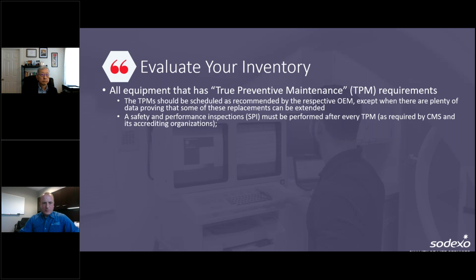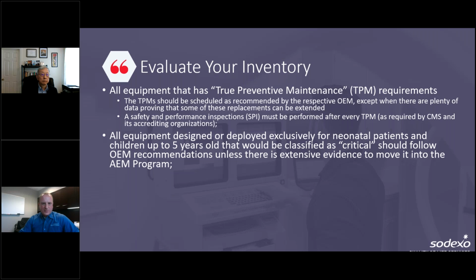So what we want to take into account is devices that what we consider true preventive maintenance. It's not just a safety and functions check. We're looking at items that require repair or replacement, routine replacement of wear and tear type items. All equipment designed or deployed exclusively for neonates. Again, this is up to 5 years old, and anything that you would classify as critical should be following the OEM recommendations unless there is extensive evidence.